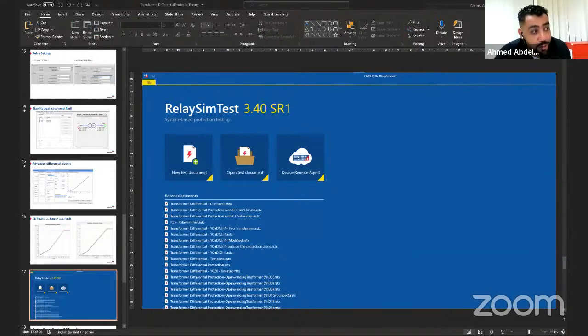I will go to the general, then fault primary, supply secondary. I will say fault secondary, supply primary. You will see that the voltage, the fault changes to the other side. The supply will be from the primary side, and it will flow inside the relay. If my system is stable in this case, it means it is stable in case I have an external fault on this side and on this side.